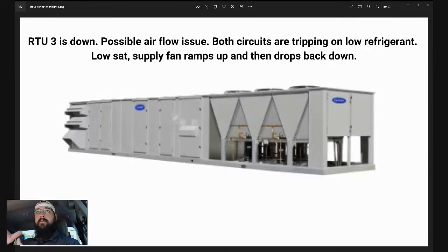So I start questioning, is there possibly a static sensor issue? Do we need to get a manometer out? Do we need to verify what my actual static pressure is? Even if you lock it off at the drive, let's say you set it at 30 hertz or set it at 40 hertz, I need to verify that that static sensor is actually reading properly.